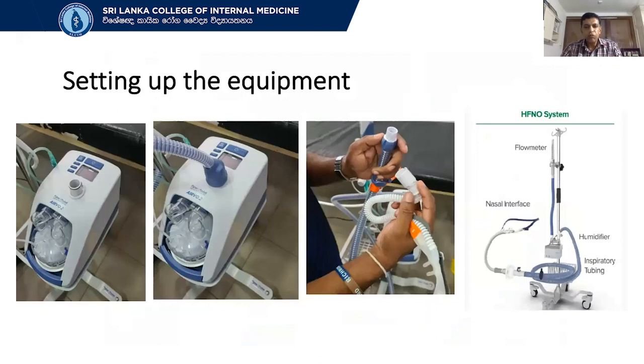So I will take you through briefly how we set this up, and this is the Fisher and Paykel machine, which we all are handling. You have the humidifier, and then the tubing. You connect the tubing, and you connect on your right the nasal cannula to the tubing, and once you do that, this is how the machine looks like. And you need a source of water to the humidifier, auto filling. What we usually use is, we don't have the set water bag, so we fill a saline bag with lukewarm water and we hang it up, and then usually the humidifier automatically fills up.